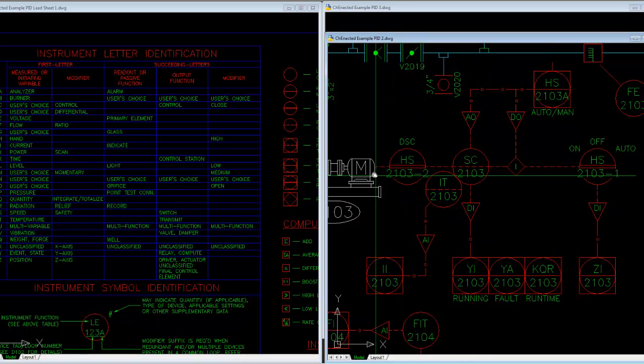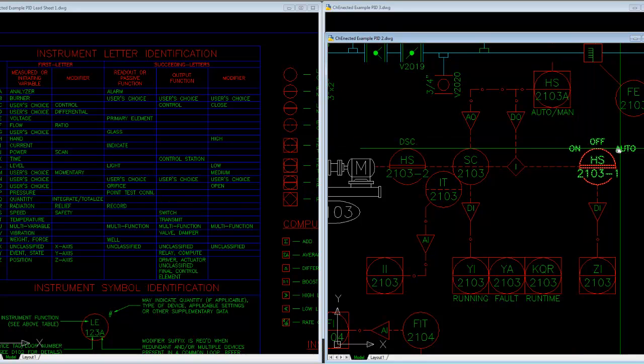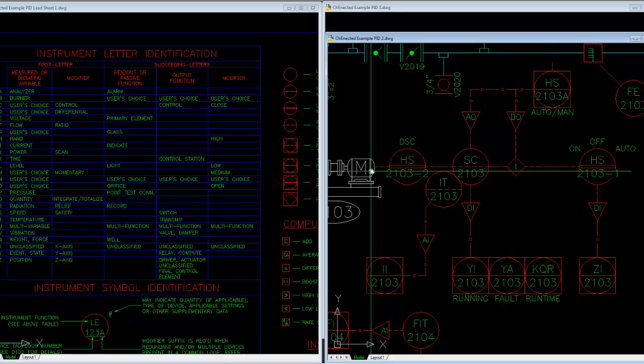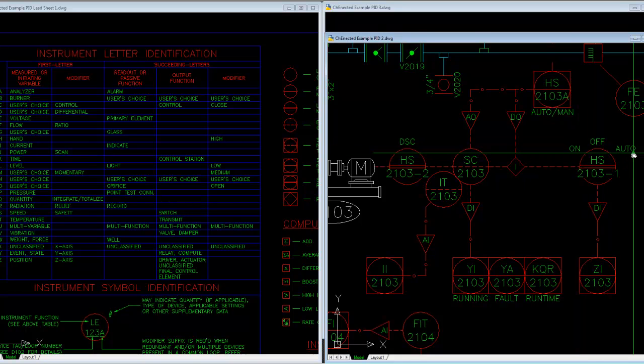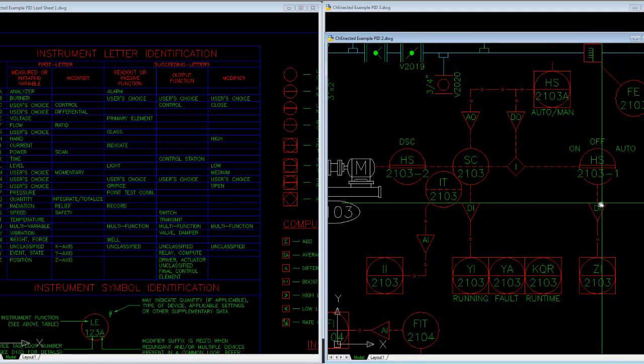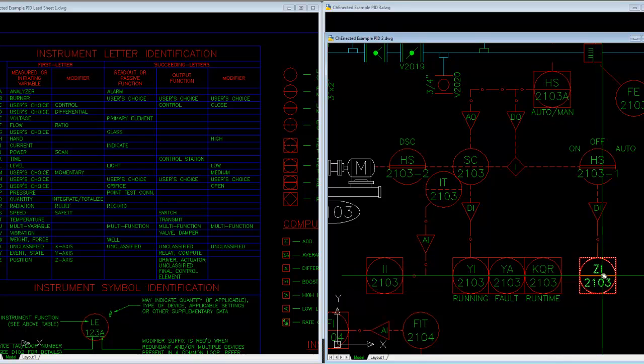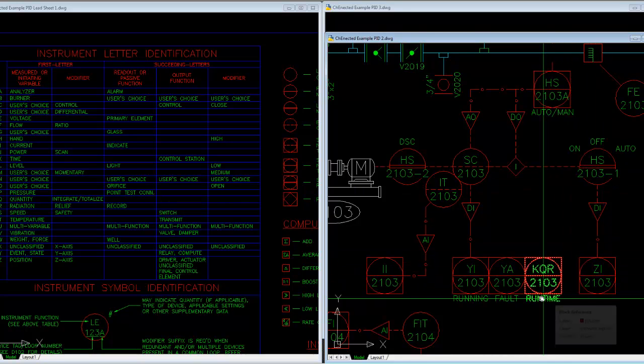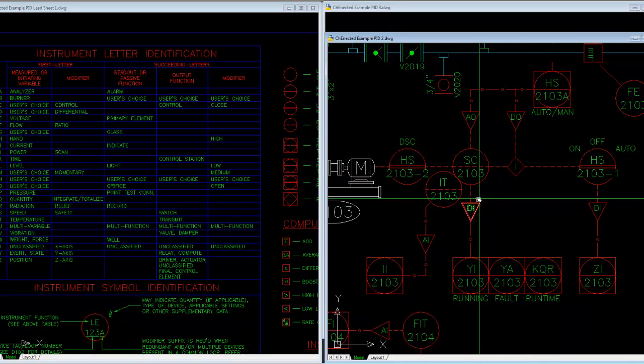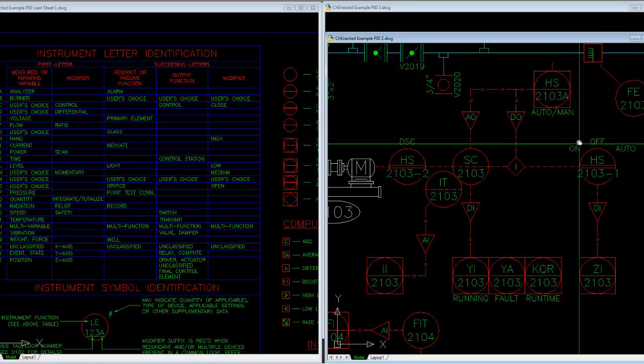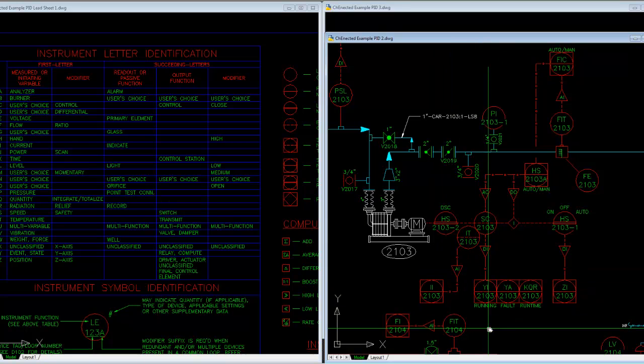Coming down the lines, we see the electrical symbol that's part of the driver system operating the motor, and then a hand switch on a local panel that we can use to start, stop, or place the motor in auto — which provides remote functionality from the control system. When placed in on it will run; off it will never run; in auto you have functionality from the HMI or DCS, and the system knows it's in auto because there's a digital input provided. That input is not labeled here and it probably should be — I would copy over 'runtime' and change it to 'auto' to indicate that input is for when that switch is in auto, because if a guy at the control system is trying to run the motor and the field hand switch is set to off, he may not know why the motor won't run.